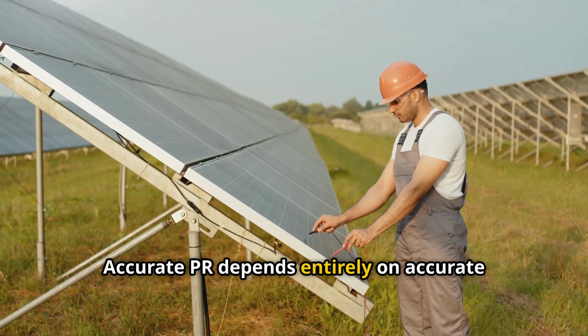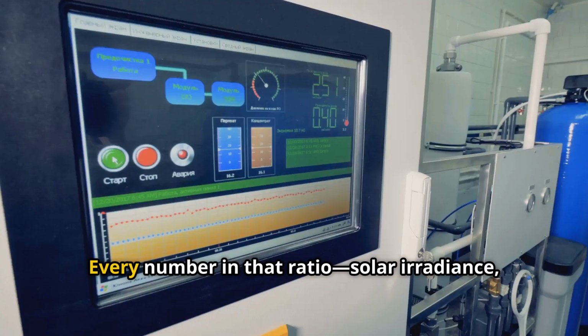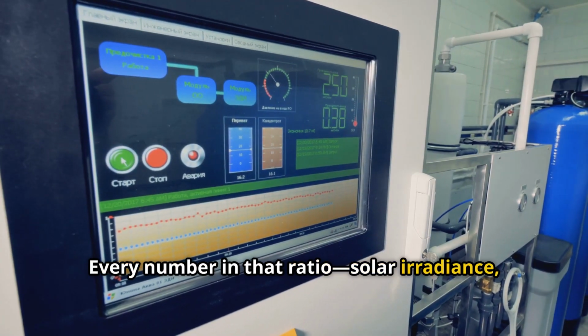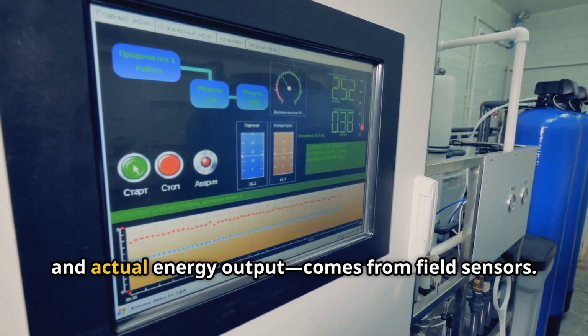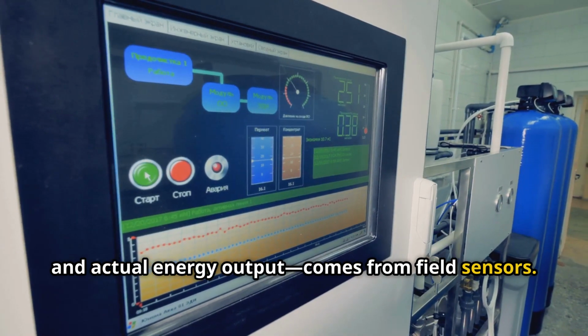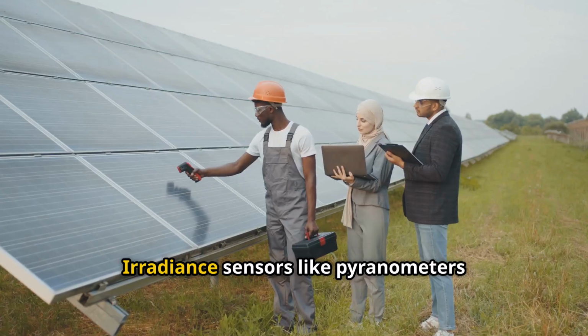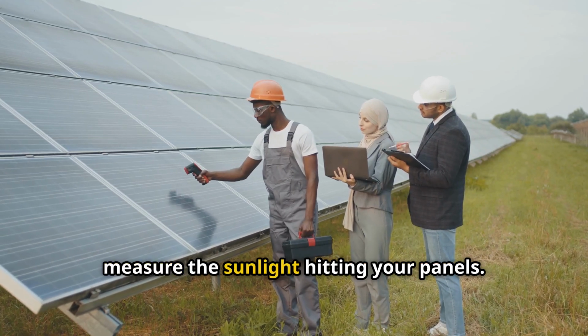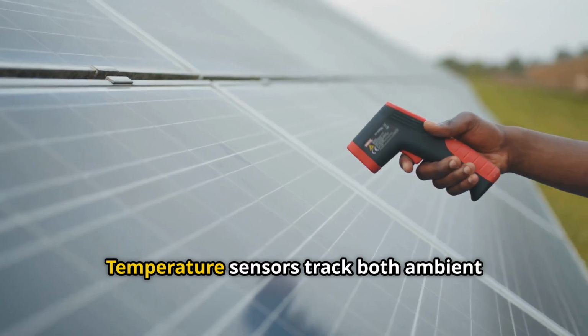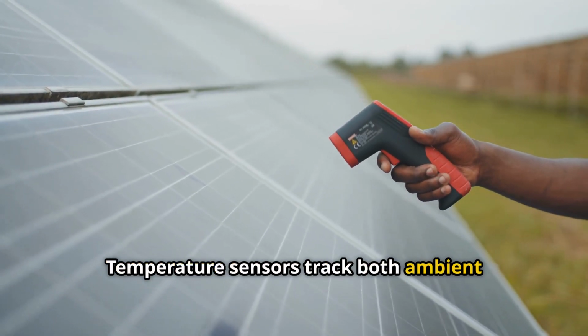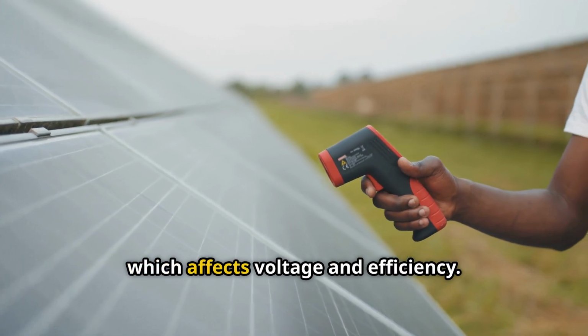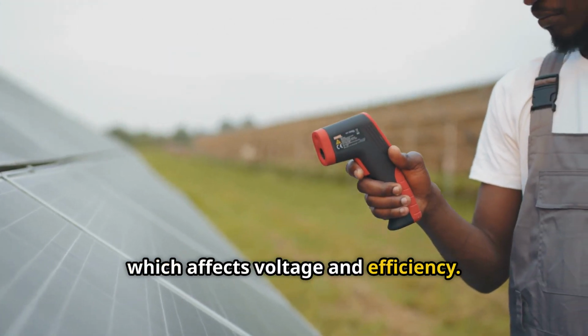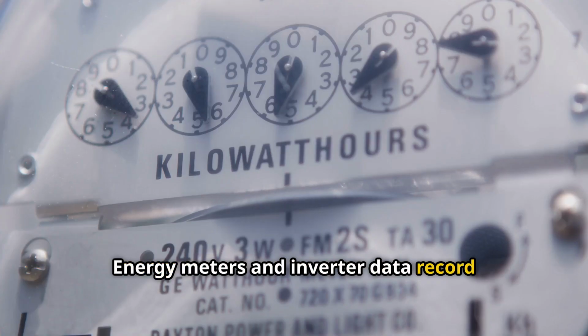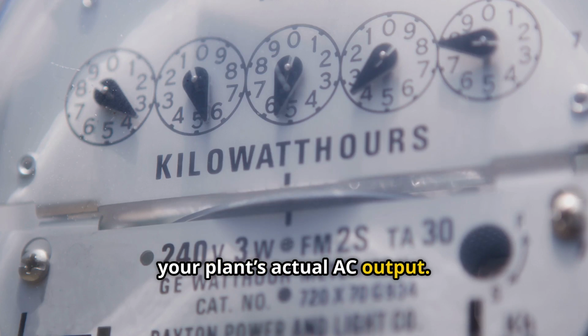Accurate PR depends entirely on accurate sensor data. Every number in that ratio, solar irradiance, panel temperature, and actual energy output comes from field sensors. Let's break it down. Irradiance sensors like pyranometers measure the sunlight hitting your panels. Temperature sensors track both ambient and module heat, which affects voltage and efficiency. Energy meters and inverter data record your plant's actual AC output.